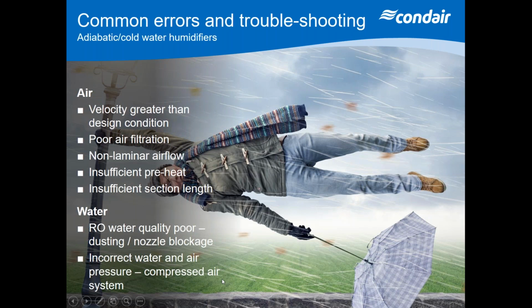To look at also common errors with adiabatic systems, if you're looking at an adiabatic adaptive system, we commonly see with commissioning that when we get a design, it's 10% higher when they get to the commissioning stage because of the air balancing side of things. Now, if that's selected right on the cusp of the maximum velocity, you're going to find that you might have carryover issues. And this is very prevalent now, obviously, with the requirements to up the fresh air rates. So if you're up on the fresh air rates, you might be increasing your air volumes as well, possibly, and that will have an effect on the unit.